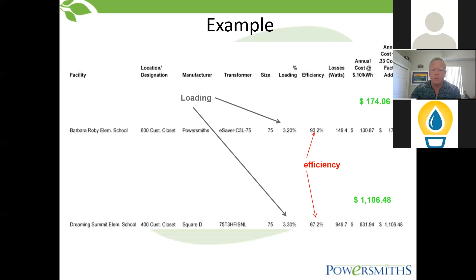This is the state of Delaware. They had these facilities, not DOE, it's the Department of Health facilities, DOH. They had the same building all across the state of Delaware, and all they did was duplicate the building so that every one had a 300 kVA transformer, and you could see the loading profiles of all these 300 kVAs. They were sitting there going, why are we putting in such a large transformer? And I told them, well, by code you have to, because the engineer designed the building to handle this much capacity, amperage, and by code you have to have the 300 kVA transformer. All the engineers, I'm an electrical engineer, and you don't oversize things, but you have to go by code and then put a little CYA in there. So that's what you have to do.